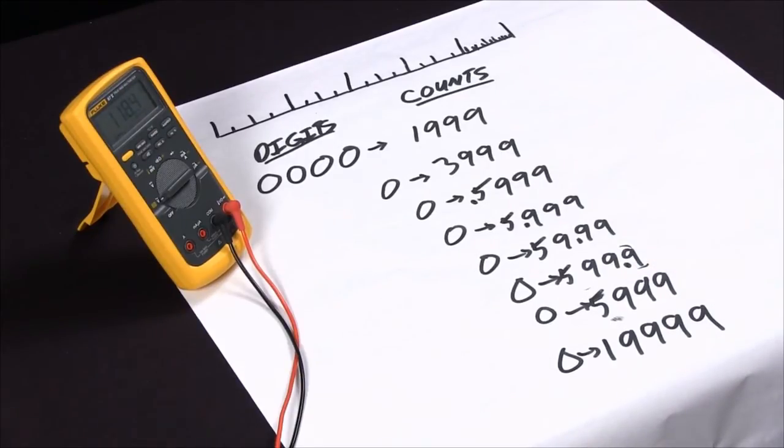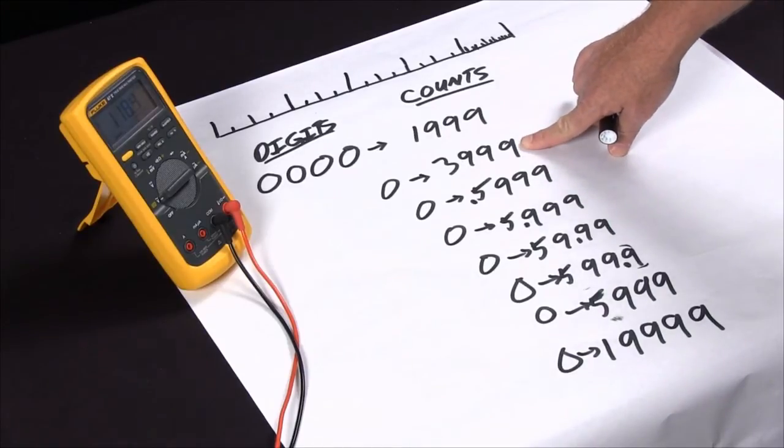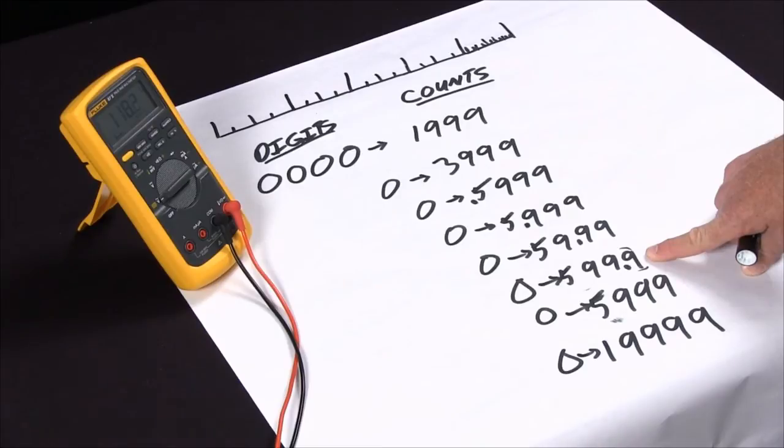Why we went to 6,000 counts is with this meter, it would range up at 400 volts. You would not be able to see 480 volts with a tenth of a volt resolution. So by going to 6,000 counts, we've actually given you a little extra in your meter that you didn't expect.